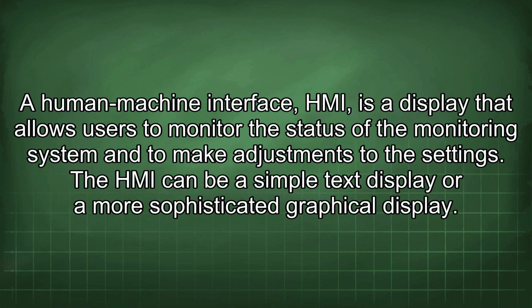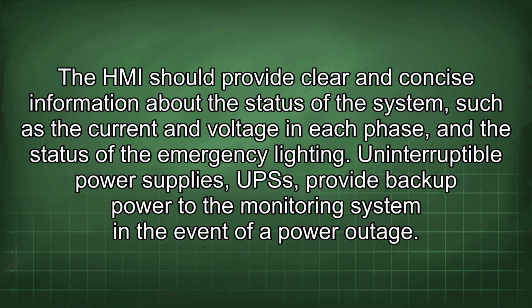A human-machine interface, HMI, is a display that allows users to monitor the status of the monitoring system and to make adjustments to the settings. The HMI can be a simple text display or a more sophisticated graphical display. The HMI should provide clear and concise information about the status of the system, such as the current and voltage in each phase, and the status of the emergency lighting.